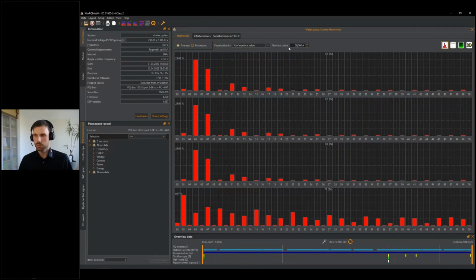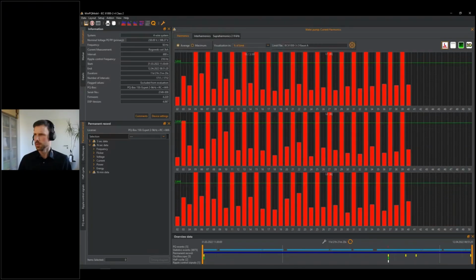If I go with 50, PQMobil calculates everything new, and now the values in percent of the nominal value change, of course. So you can play around and do some experiments with that. Now I go to in percent of the limit, but which limit? For the limit, I have different opportunities. So we can compare the values of the measurement data against different limit values.